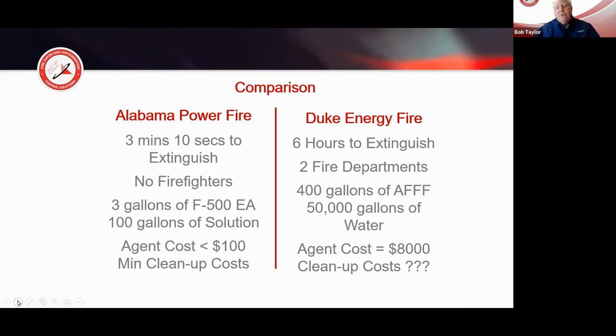See, Alabama Power went through the process of continual improvement. They detected a concern and worked to correct it in order to prevent it, putting an F500 encapsulating agent control concentrate supply system on their fire system for the transformer. When they had the big oops and something went wrong, it took 3 minutes and 10 seconds to extinguish the fire without any firefighter response. They used 3 gallons of F500 and about 100 gallons of overall solution, less than $100, with very minimal cleanup needed, because F500 encapsulating agent is biodegradable and recognized even by the US EPA as a soil remediation agent.